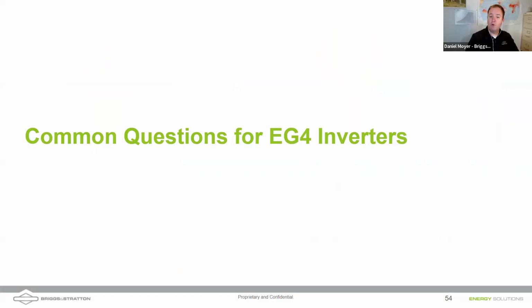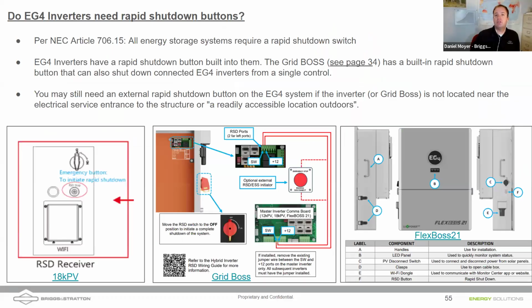Thinking about working with EG4, I had a couple of questions, and I was just curious. All of these systems need to have rapid shutdown buttons, right? So that if the fire department emergency responders show up to the house, they're going to kill power to the house by flipping off the main breaker, maybe taking their fire axe to the meter and knocking it out of its socket. But if you have an energy storage system on site, loss of grid only means that I need to turn myself on using battery and start powering home loads using the battery. So we still have live conductors in the home while the firefighters are there. Code requires that we put an emergency rapid shutdown switch in a readily accessible location so that if the firefighters show up, they can hit this button, which will shut off the output of the inverter.